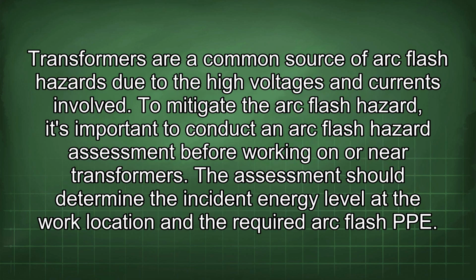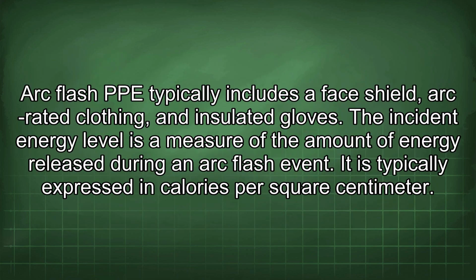Transformers are a common source of arc flash hazards due to the high voltages and currents involved. To mitigate the arc flash hazard, it's important to conduct an arc flash hazard assessment before working on or near transformers. The assessment should determine the incident energy level at the work location and the required arc flash PPE. Arc flash PPE typically includes a face shield, arc-rated clothing, and insulated gloves.